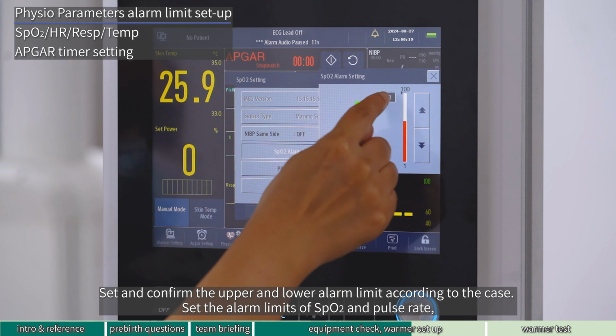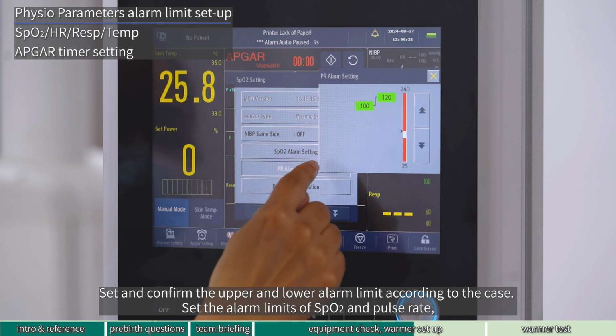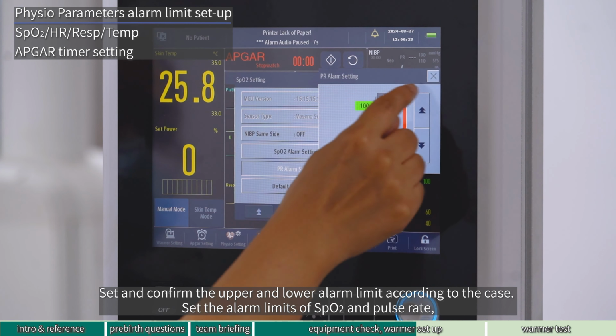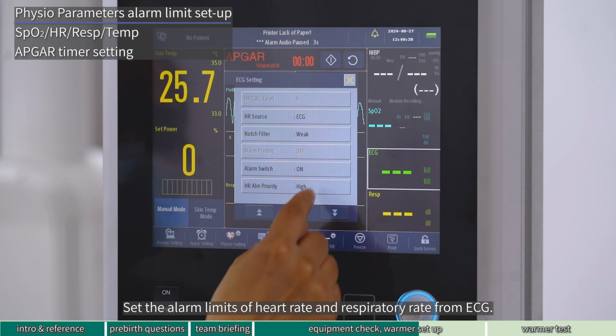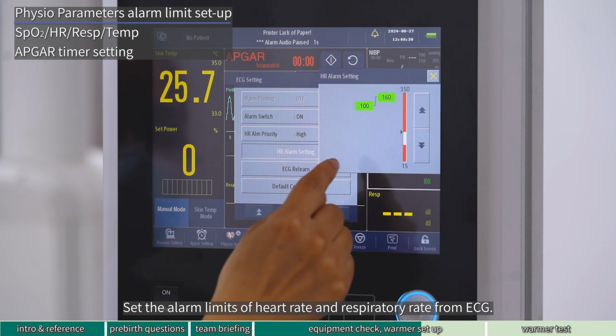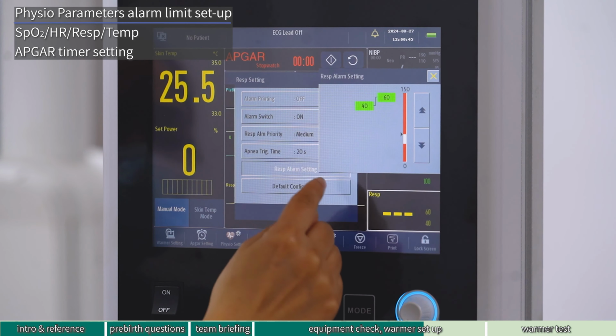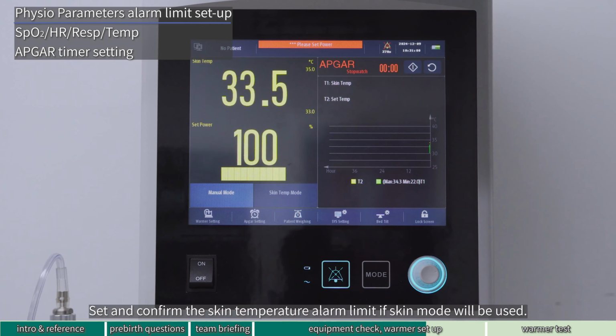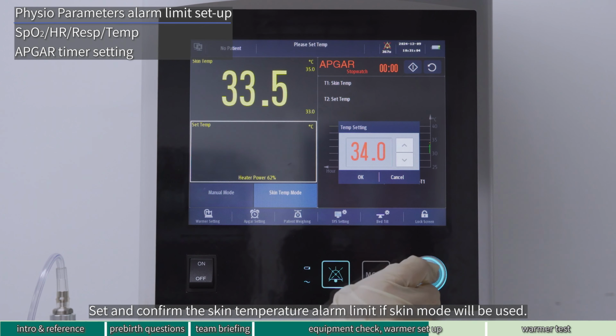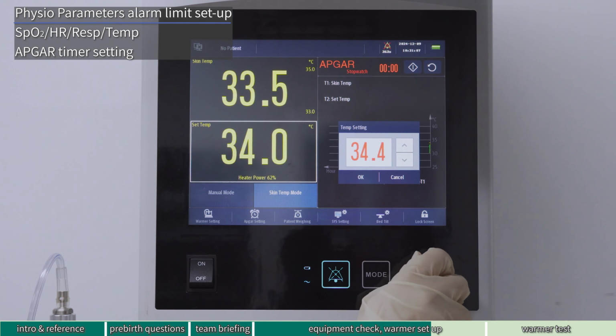Set and confirm the upper and lower alarm limit according to the case. Set the alarm limits of SpO2 and pulse rate. Set the alarm limits of heart rate and respiratory rate from ECG. Set and confirm the skin temperature alarm limit if skin mode will be used.